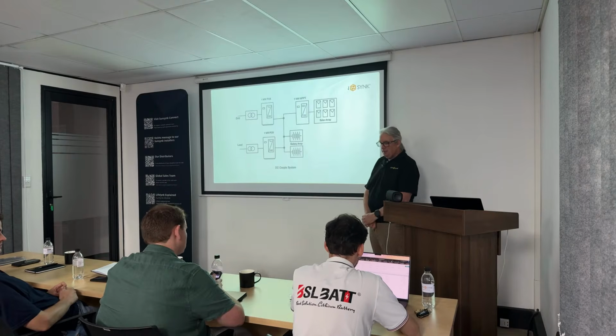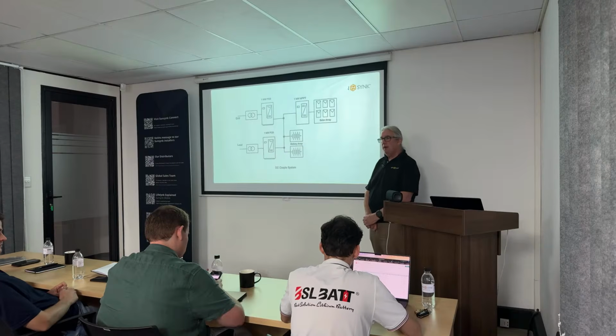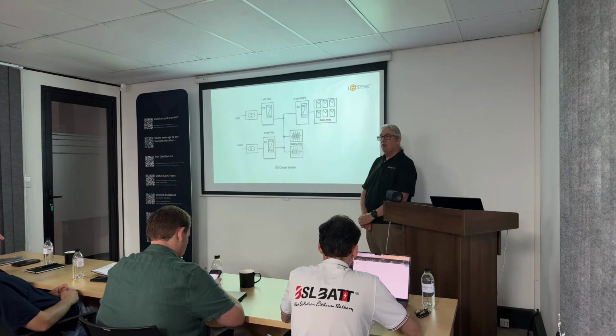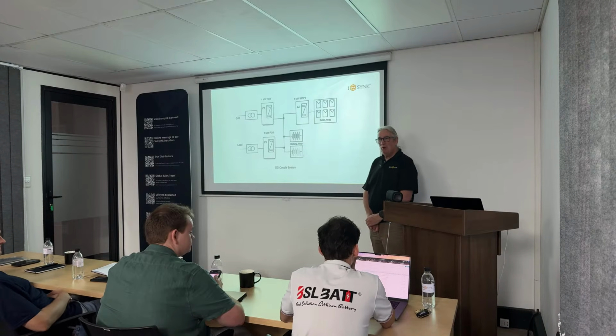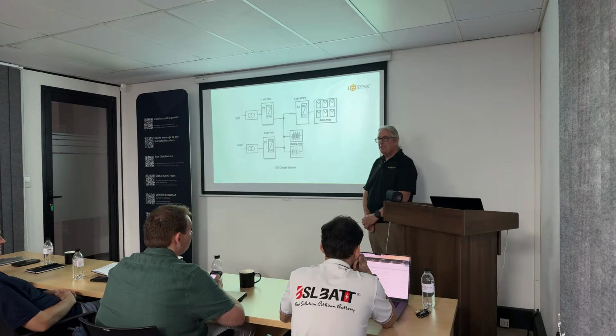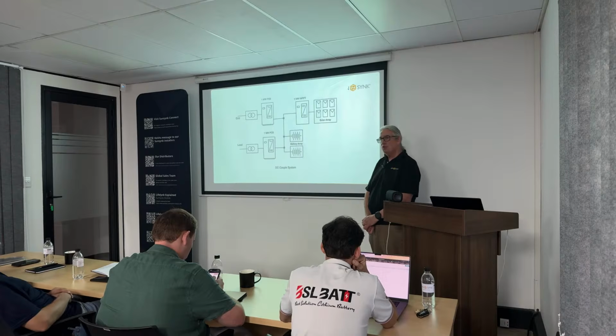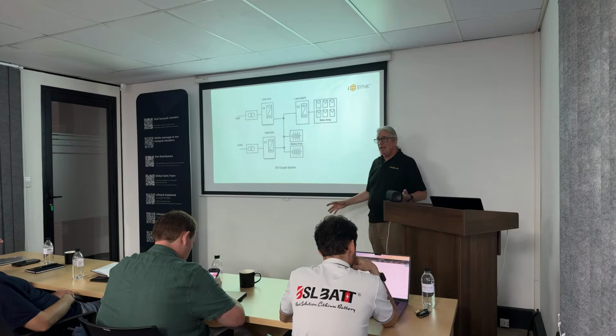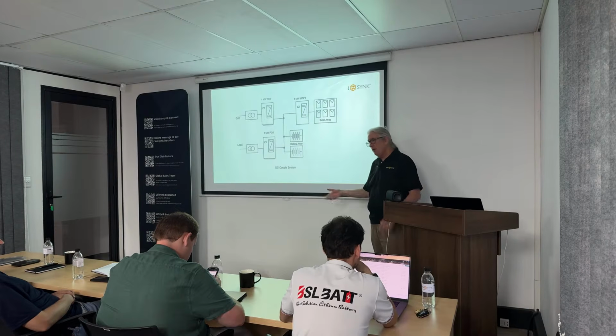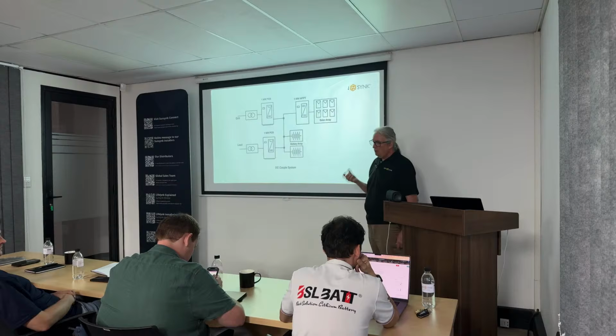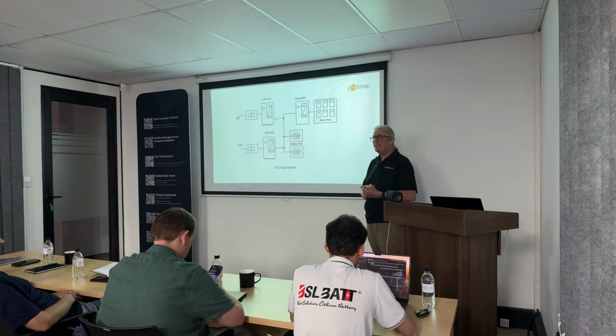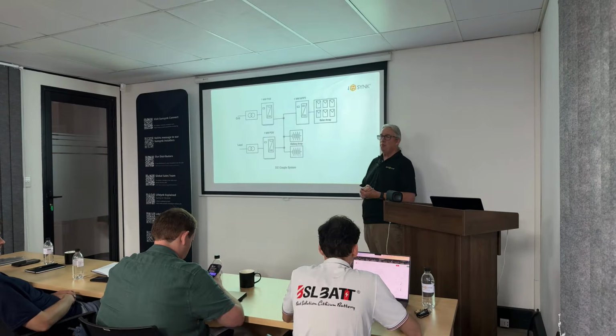The only thing I've experienced is in Hong Kong, for example, where we have to use transformers. All inverters have to be coupled with a transformer that's on grid. They produce lots and lots of wonderful harmonics, and the transformers create the harmonics. And people are not always aware of the harmonic distortion, but it's basically hidden losses. So you've got this THD, total harmonic distortion, which is massive, you lose a lot of energy and you don't see it. It's somewhere, maybe on the second, third harmonic, the 50th harmonic. And so those harmonics are caused by transformers themselves. You've also got your power factor, because transformers are reactive. And so you also have issues, power factor, and lots of problems. So generally, if you don't need a transformer, don't use one.